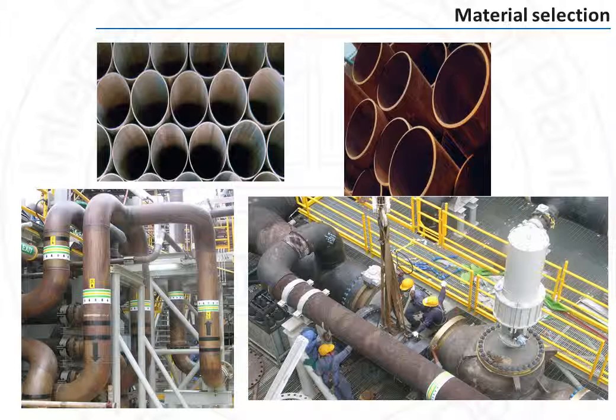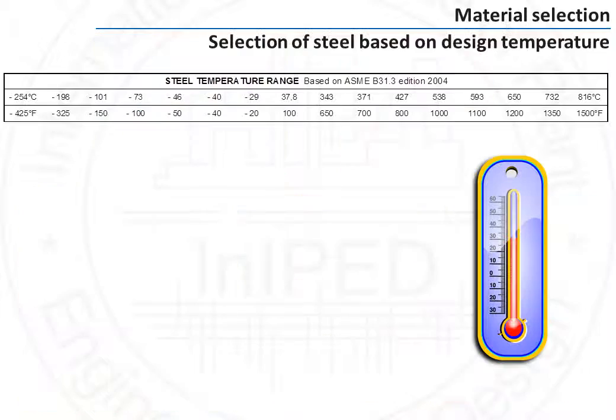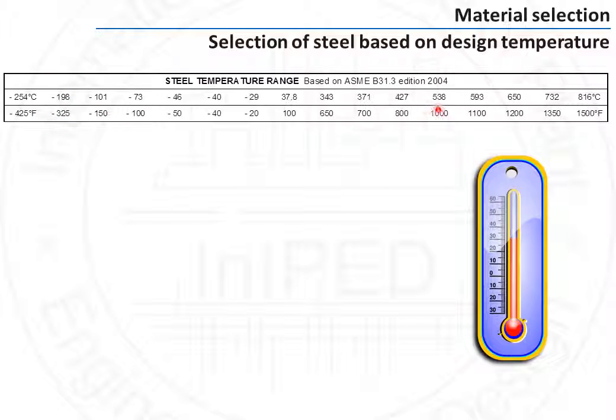The second parameter that comes into play when selecting material of construction is the fluid temperature. Both high and low temperatures to which the material could be subject have to be taken into account. For instance, carbon steel is suitable for a temperature range between minus 29 degrees Celsius to 427 degrees Celsius only. Below that, low temperature carbon steel and then alloys up to stainless steel need to be used. Above that, stainless steels also have to be used.